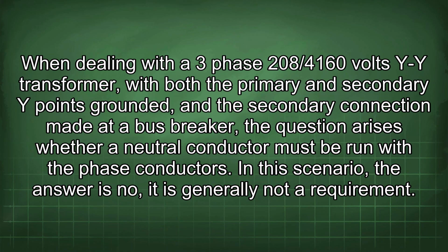When dealing with a three-phase 208/4160 volts YY transformer, with both the primary and secondary wye points grounded and the secondary connection made at a bus breaker, the question arises whether a neutral conductor must be run with the phase conductors. In this scenario, the answer is no, it is generally not a requirement.